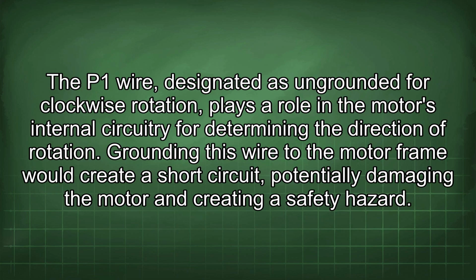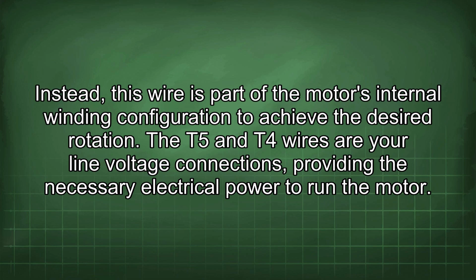The P1 wire, designated as ungrounded for clockwise rotation, plays a role in the motor's internal circuitry for determining the direction of rotation. Grounding this wire to the motor frame would create a short circuit, potentially damaging the motor and creating a safety hazard. Instead, this wire is part of the motor's internal winding configuration to achieve the desired rotation.